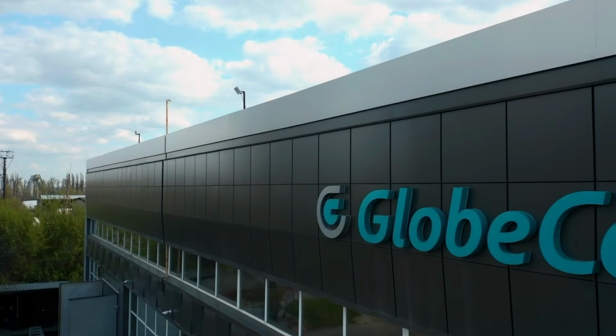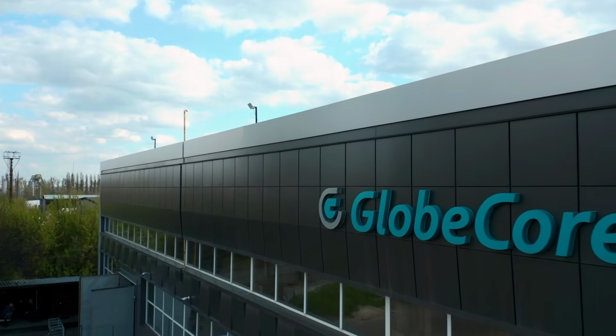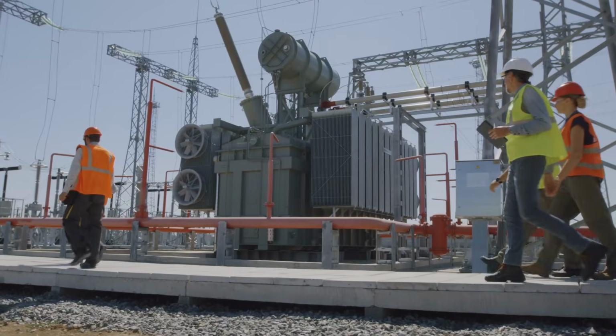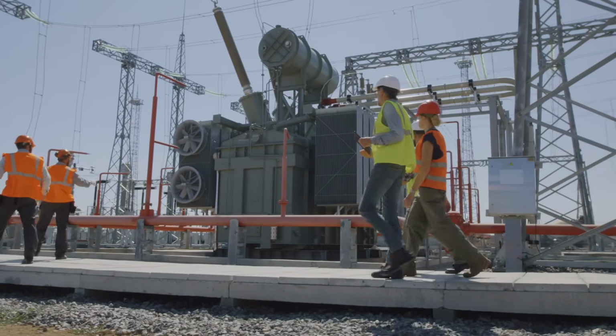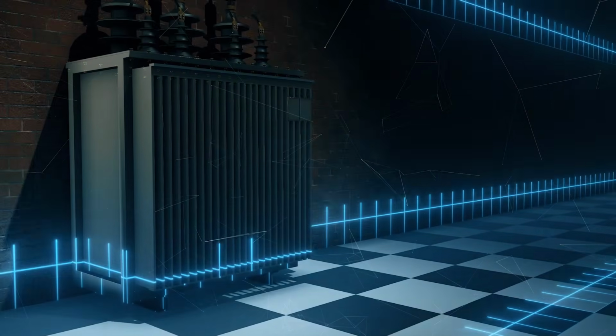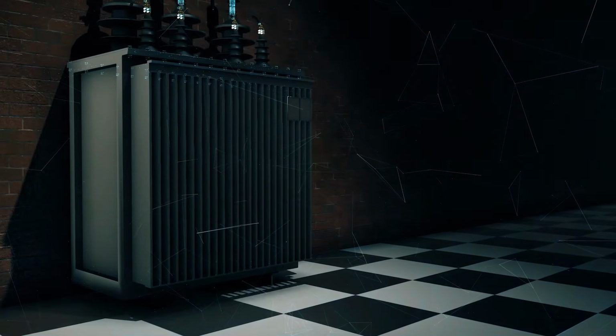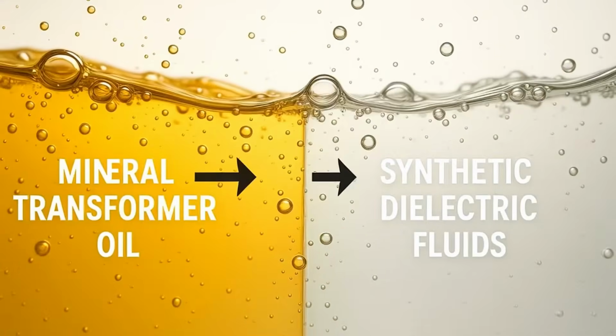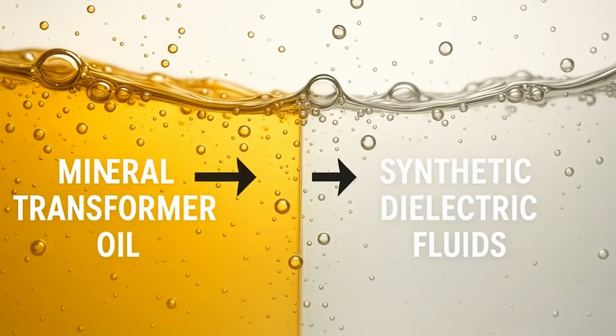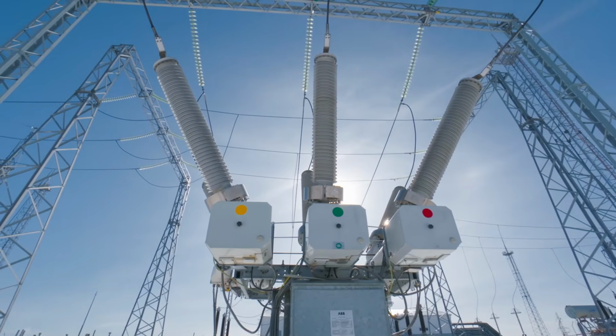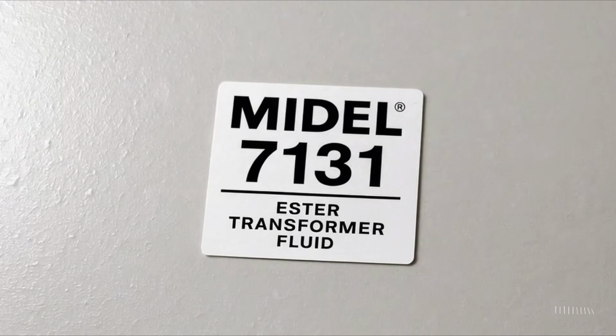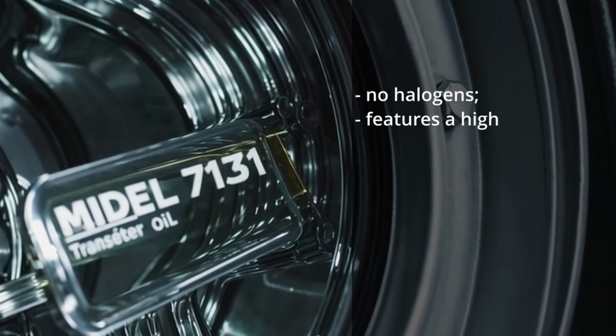With increasing requirements for safety, reliability, and environmental friendliness of power-generating equipment, more and more companies are switching from conventional mineral transformer oil to synthetic dielectric fluids. One of the most common modern solutions is MIDEL 7131, a synthetic organic ester that contains no halogens, features a high environmental performance, and ensures increased fire resistance during the operation of high-voltage equipment.